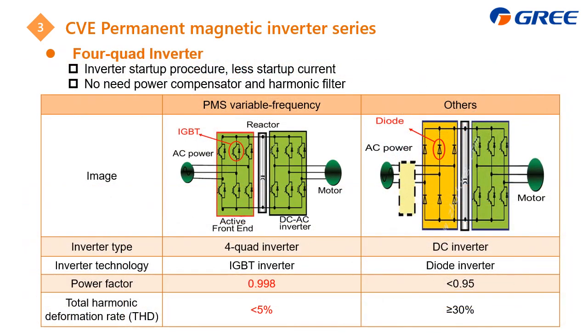Next is the device we use to change the compressor RPM. We apply the IGBT instead of this diode, which is common for the regular air conditioner. The benefit is that the power factor, compared with this one, is definitely higher. And the most important is the total harmonic distortion rate. It is less than 5%, and for this diode, it is more than 30%. So with this one, there's no need for a power compensator or a harmonic filter. And of course, it can be customized.